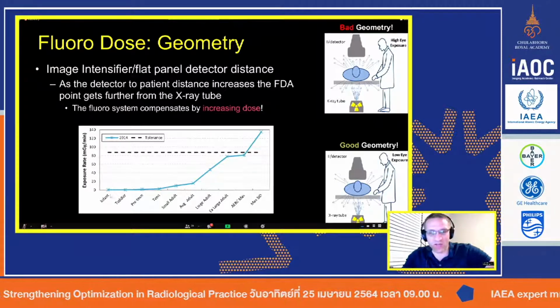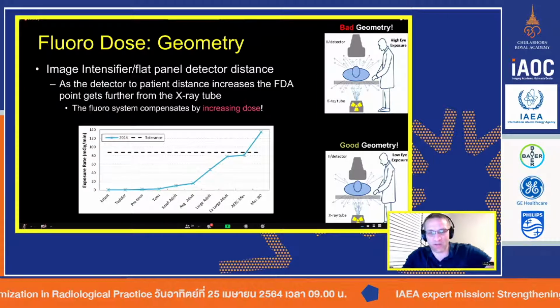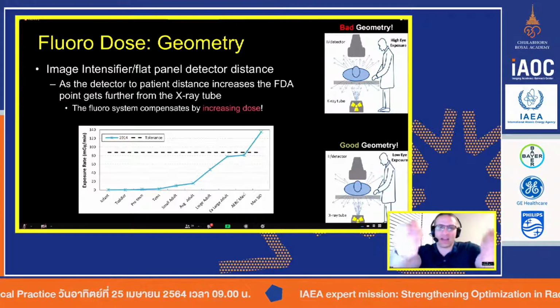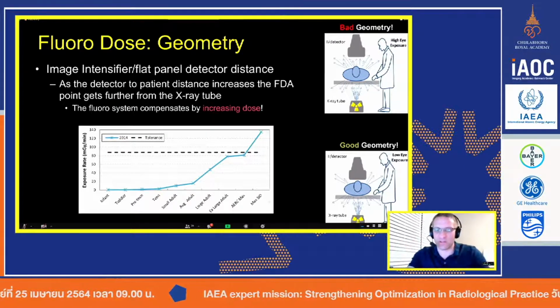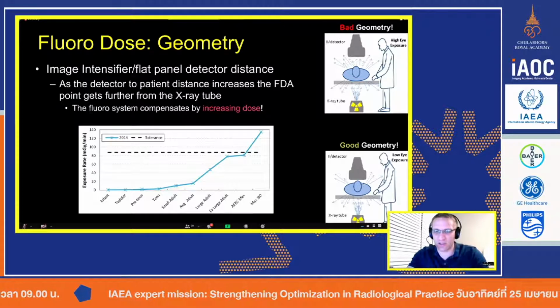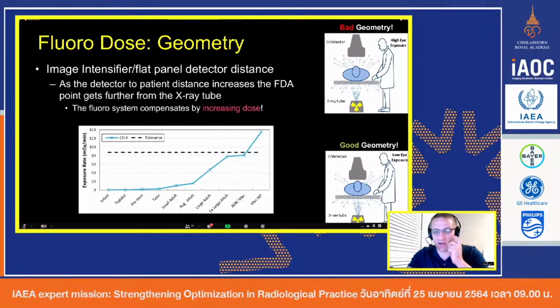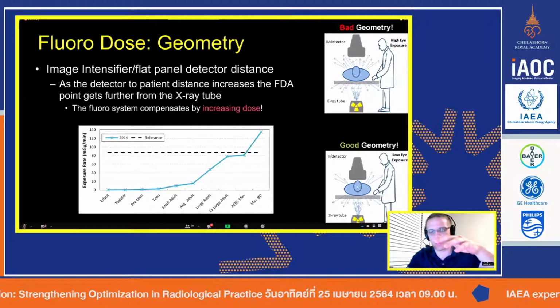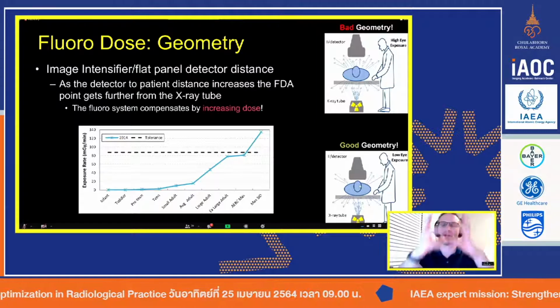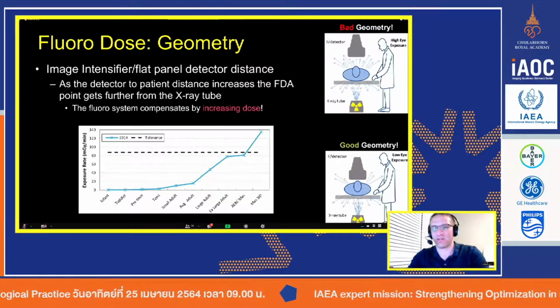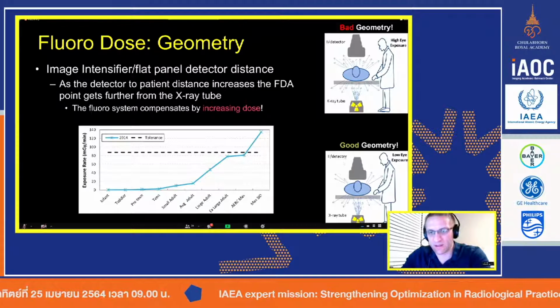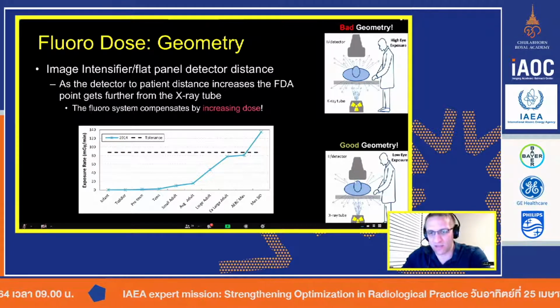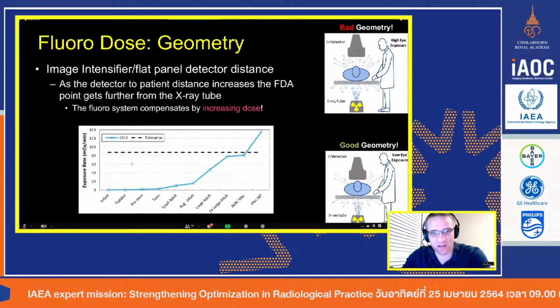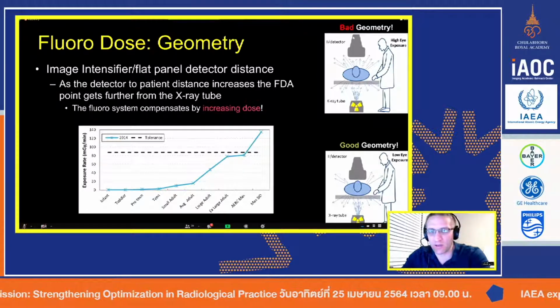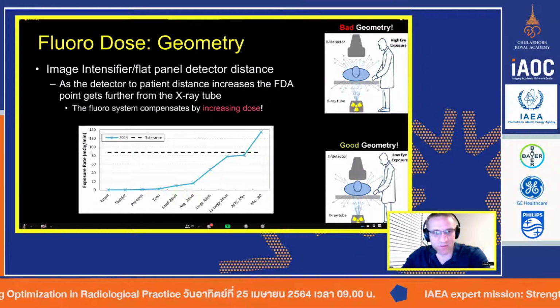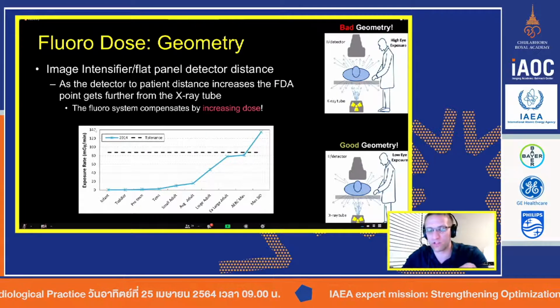I can go in and use all my blocks of plastic I've been talking about to mimic all my different sized patients. In fact, I can actually put lead into my beam. So if I have my II or my flat panel right next to my patient or phantom, where it's supposed to be, and I put everything I can possibly think of, lead and everything, so I make the system use all of the radiation it possibly can to penetrate my phantom, if the II is at its proper location, the dose should not exceed my threshold. Now, if I move it up, it will exceed that threshold. You can see how it goes from 87 all the way up to 140 in this one particular machine.